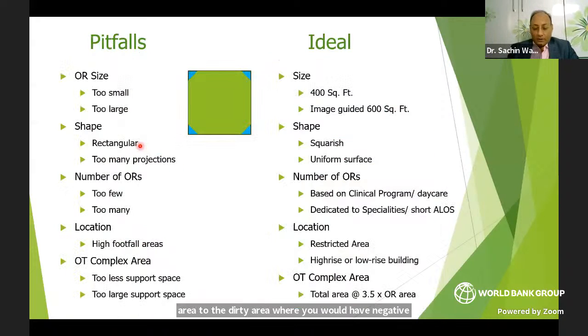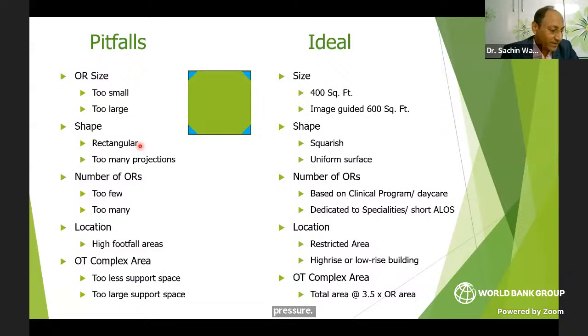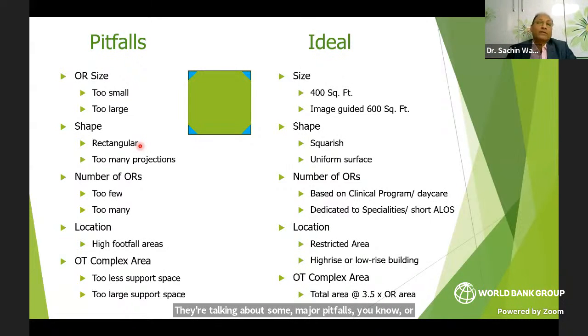Now, talking about some major pitfalls, or mistakes that people usually make, that we have encountered. Starting with the sizes of the OT, either they are too small or too large. What is recommended usually for a general specialty OT is to have around 400 square feet, which is roughly 20 by 20 square feet. As the specialty increases, as you go into neurosurgery, cardiovascular surgeries, and robotic surgeries, the space could increase to 550 square feet. And image guiding would obviously need around 600 square feet, to accommodate the imaging components.